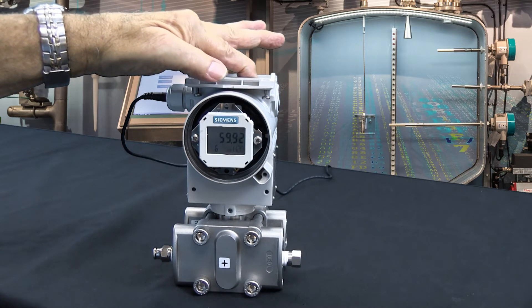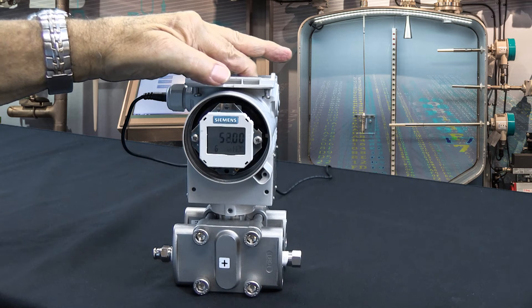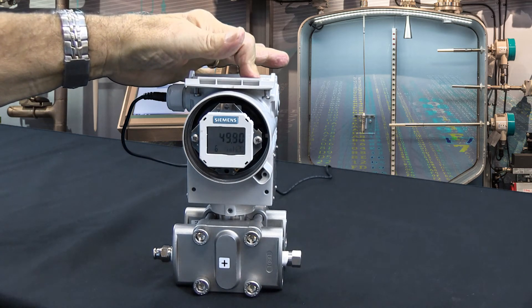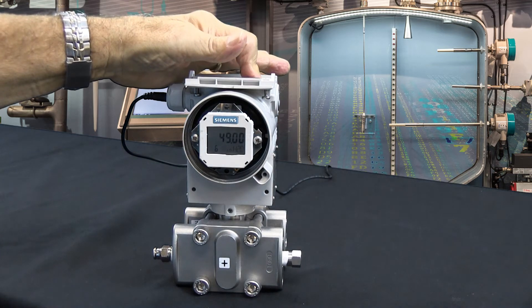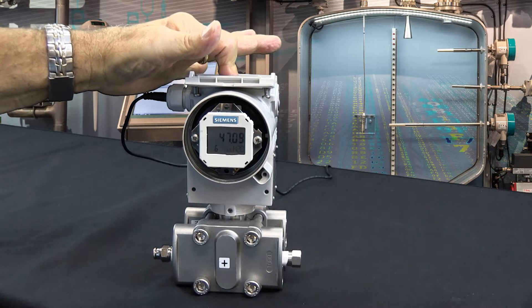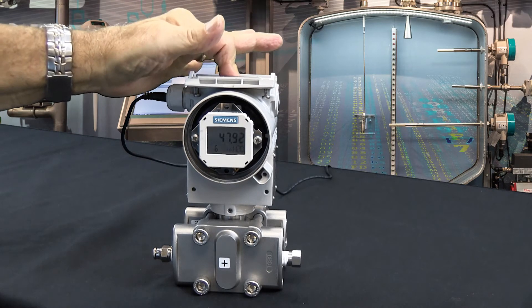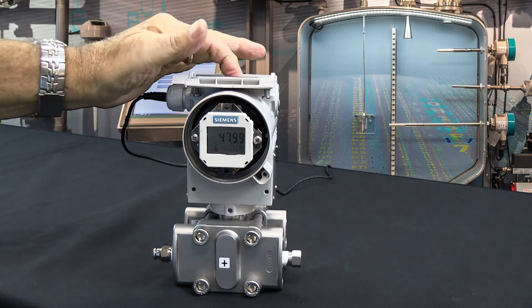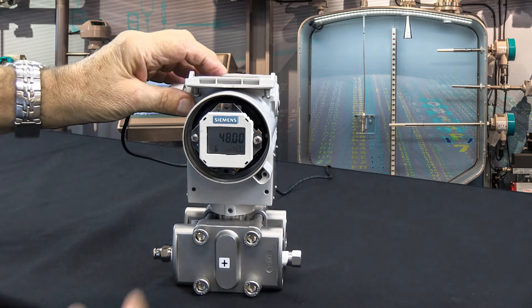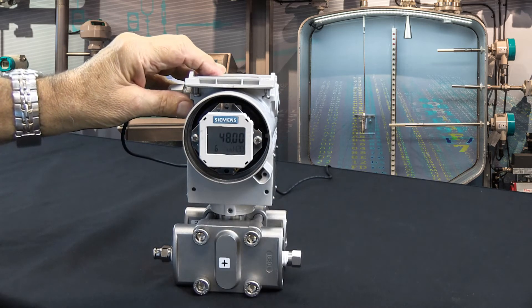So what I would do is hold the down button and it'll start scrolling down and it'll increase speed. I'll scroll down again — I overshot — so now we're going to come back up and sneak up on 48, and there's 48 exactly. So 0 to 48 inches equals full scale.